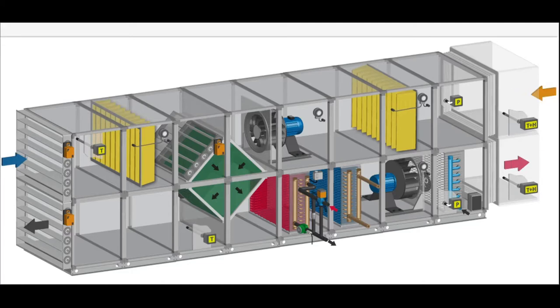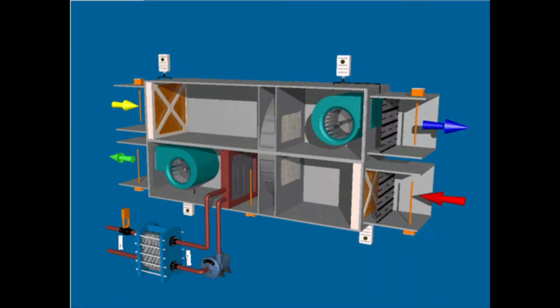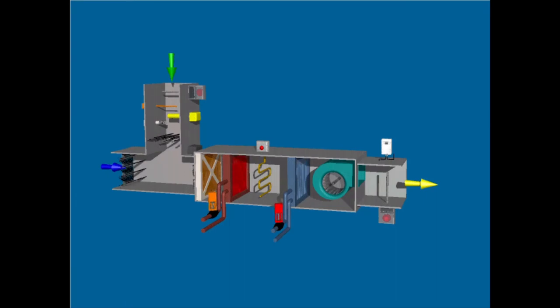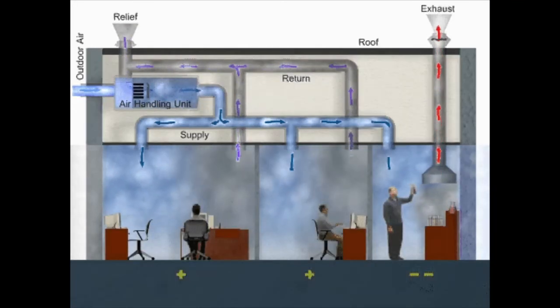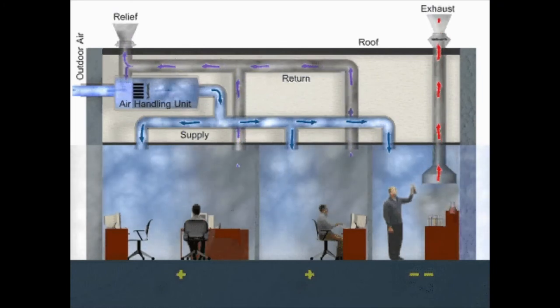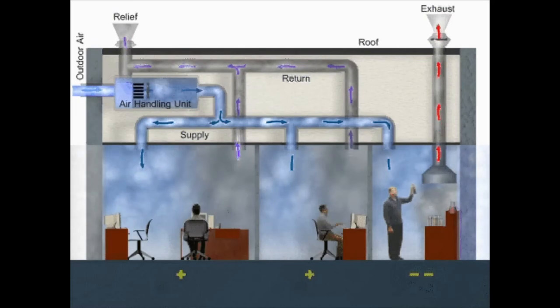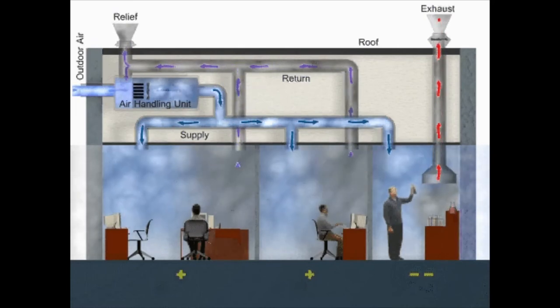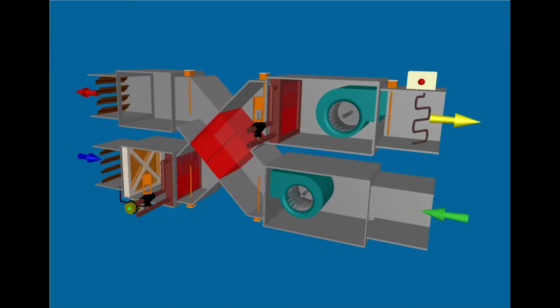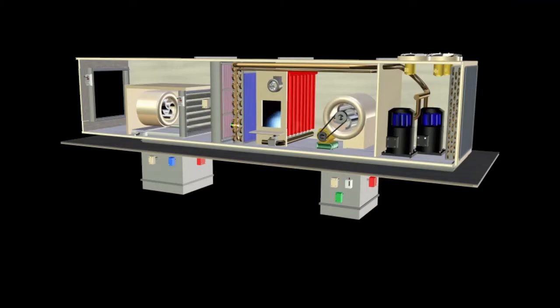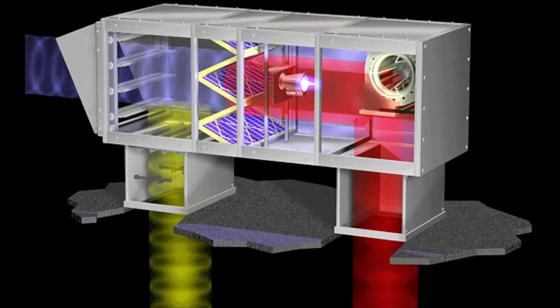Joe, you want to talk a little bit about the displacement ventilation? Sure. With a displacement ventilation system, one of the ideas is that you are basically displacing the hot air to the top of the ceiling. You would typically introduce slightly cooler than room air, maybe 60, 65, into the space, low and at a very slow velocity. It stays close to the floor until it finds a heat source and creates a plume, like a person. The hot air rises and cools you off with a relatively room neutral temperature.